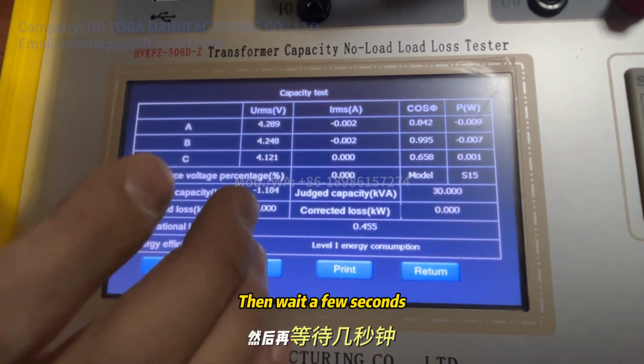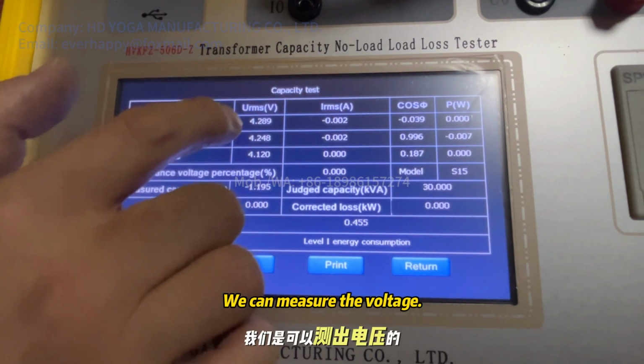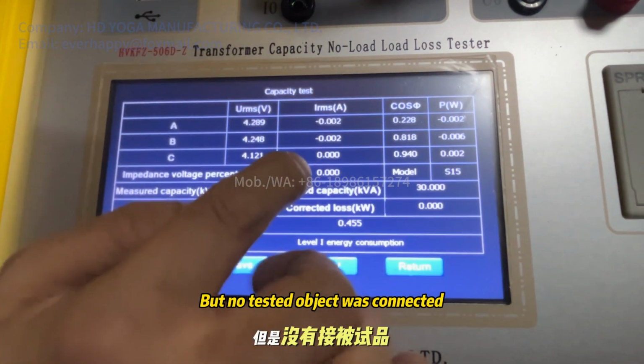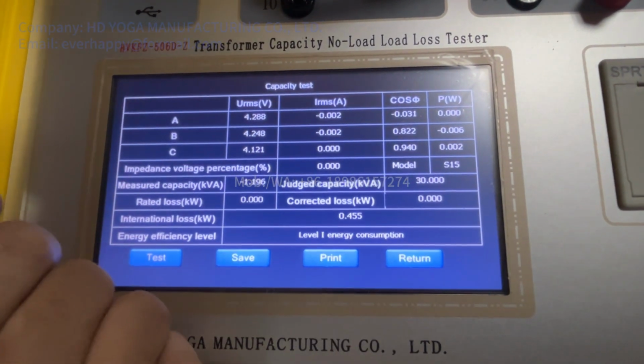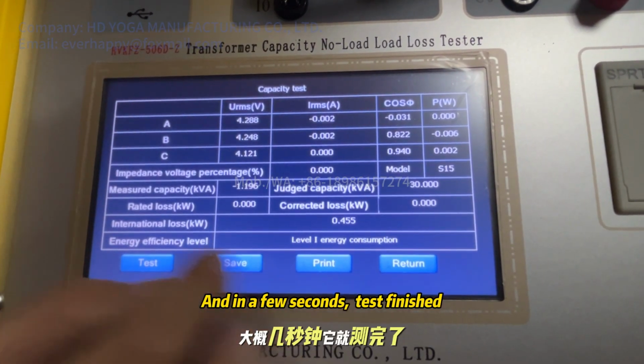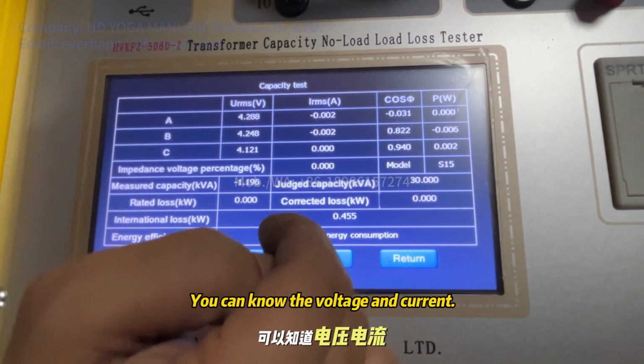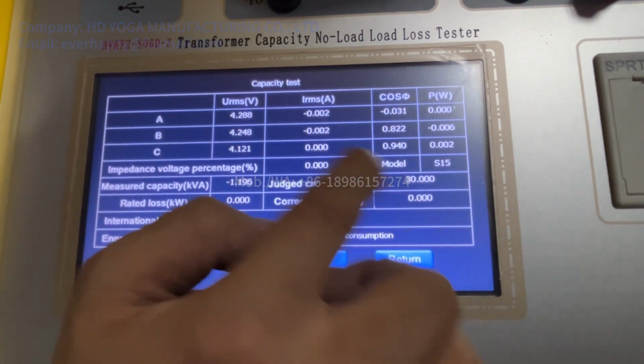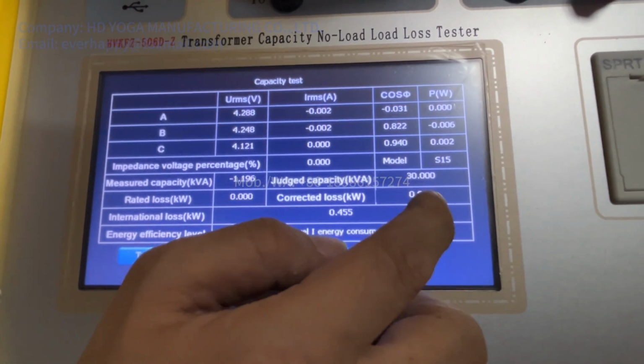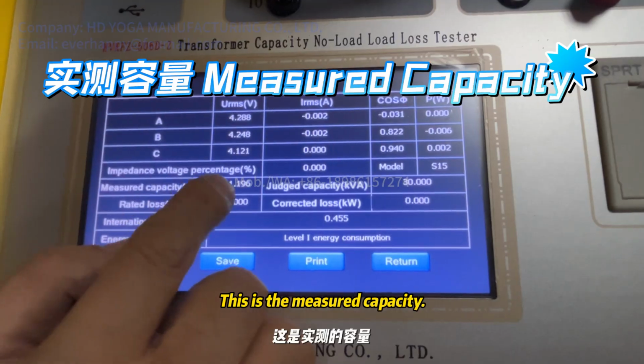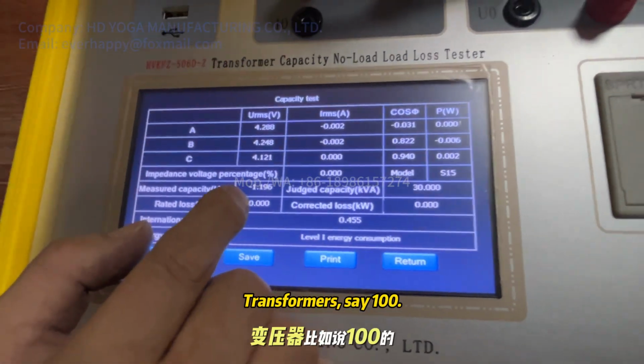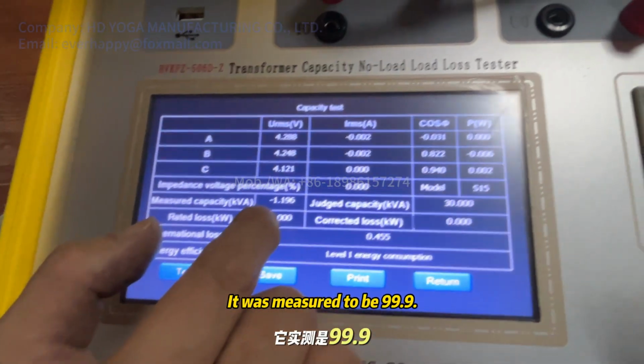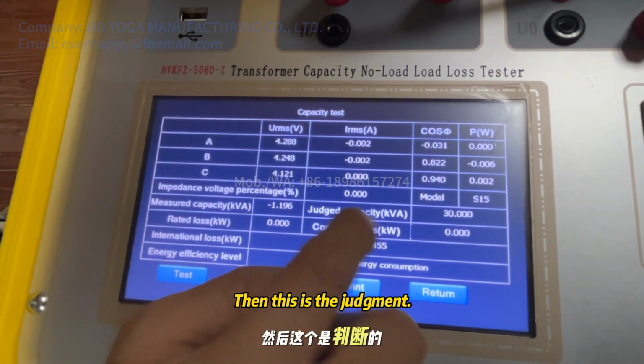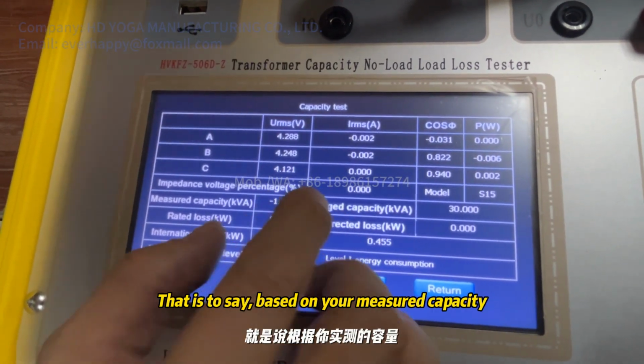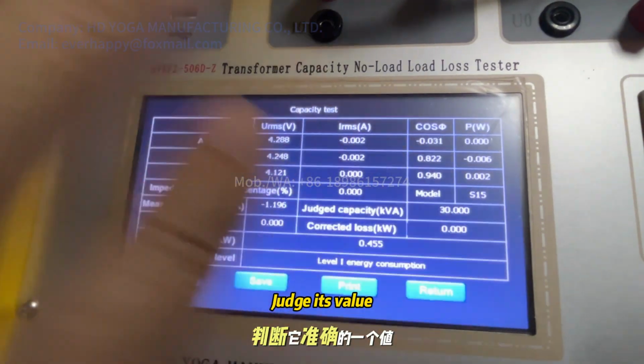Then wait a few seconds, because at this time, we can measure the voltage, but no tested object was connected. It has no current. And in a few seconds, test finished. You can know the voltage and current. Power factor is power. Model of transformer. This is the measured capacity. Transformers say 100. It was measured to be 99.9. Then this is the judgment. That is to say, based on your measured capacity, judge its value.